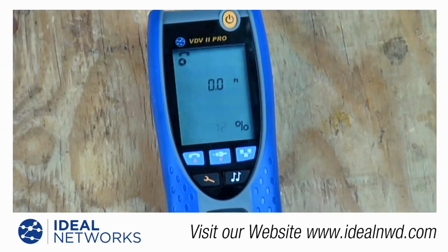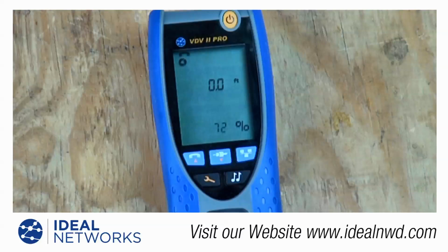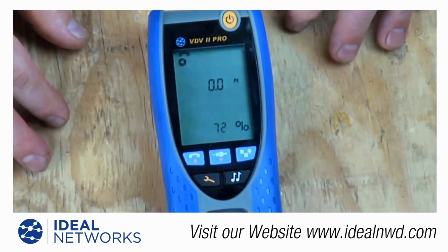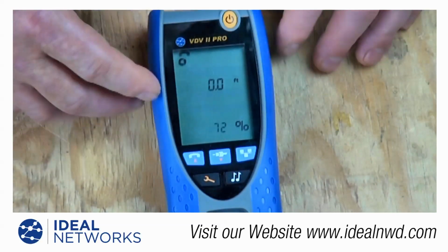The tester has a time domain reflectometer built in, used for measuring length in cables, and it can be done very accurately. You have to know what's called the nominal velocity of propagation of the individual cable you're testing, because it varies between coax and data networking cables. You can measure length on any type of cable, even Romex, but they all have a particular nominal velocity of propagation.